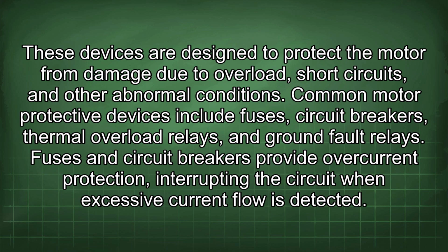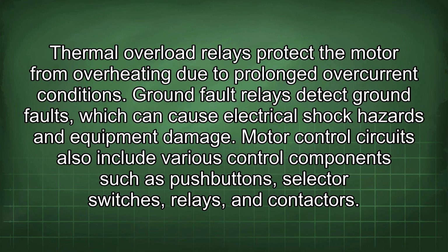These devices are designed to protect the motor from damage due to overload, short circuits, and other abnormal conditions. Common motor protective devices include fuses, circuit breakers, thermal overload relays, and ground fault relays. Fuses and circuit breakers provide overcurrent protection, interrupting the circuit when excessive current flow is detected. Thermal overload relays protect the motor from overheating due to prolonged overcurrent conditions. Ground fault relays detect ground faults, which can cause electrical shock hazards and equipment damage.